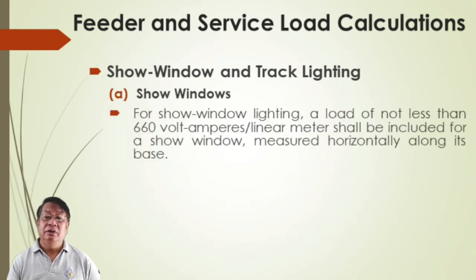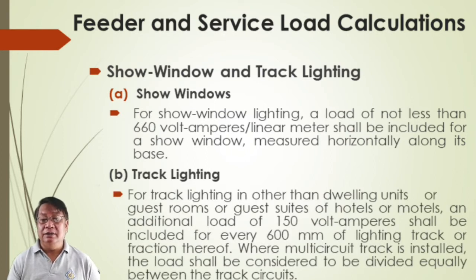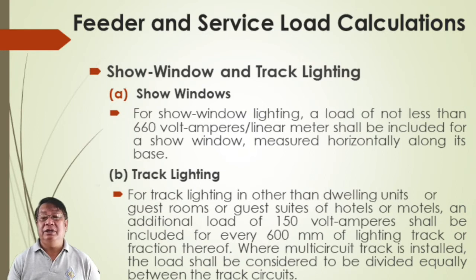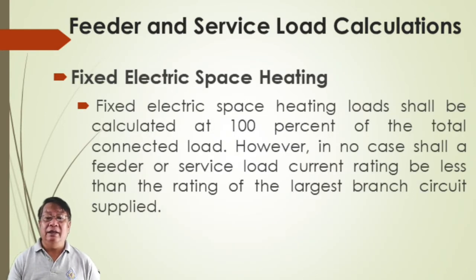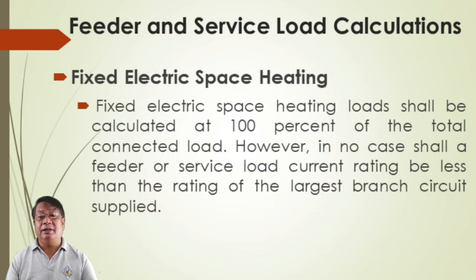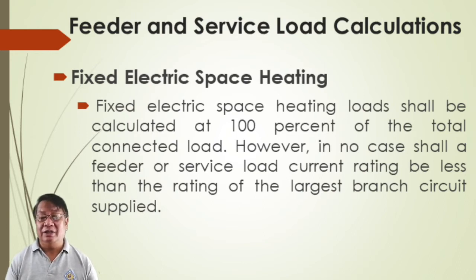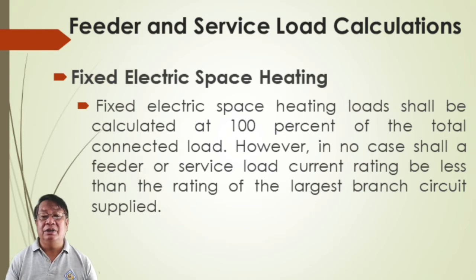For track lighting other than dwelling units, an additional load of 150 volt-amperes shall be included for every 600 mm of lighting track. Fixed electric space heating load shall be calculated at 100% of the total connected load — there is no demand factor applied. 100% should be considered for the feeder or service load for electric heating.